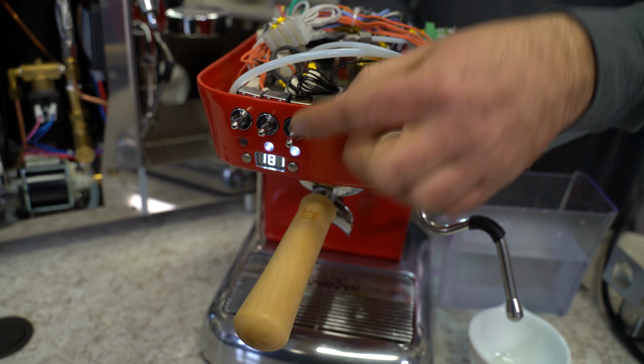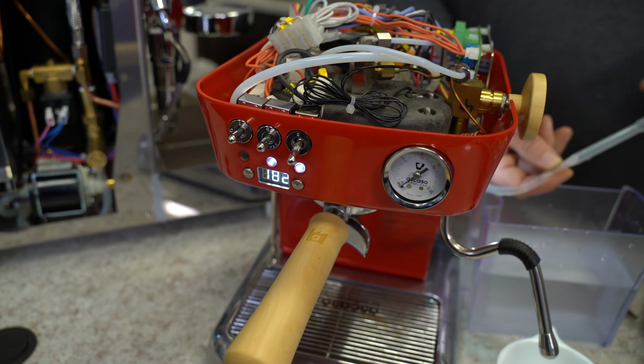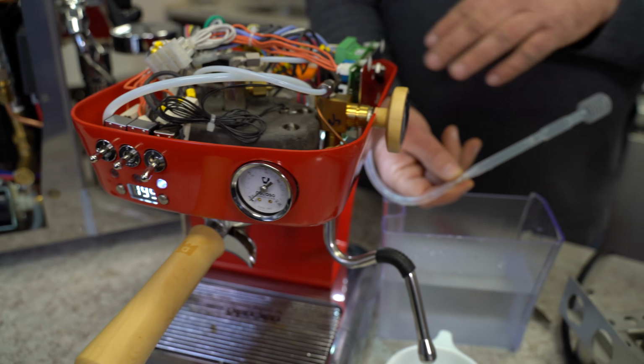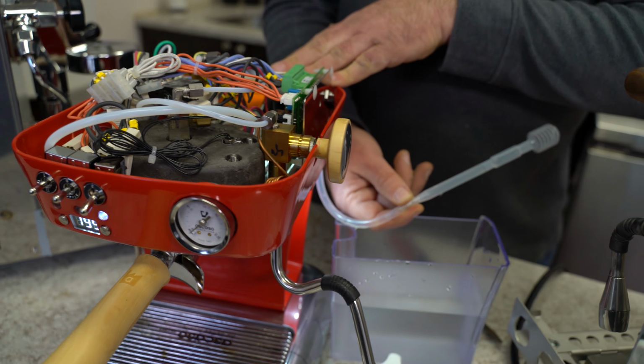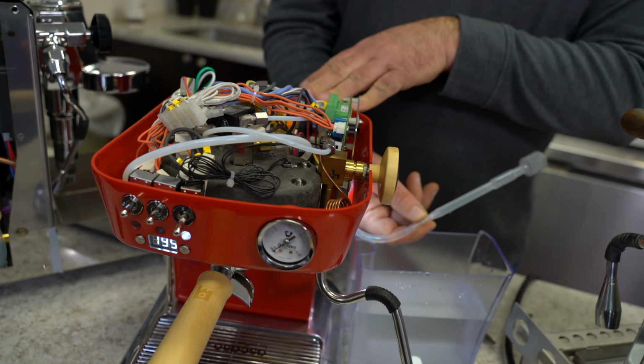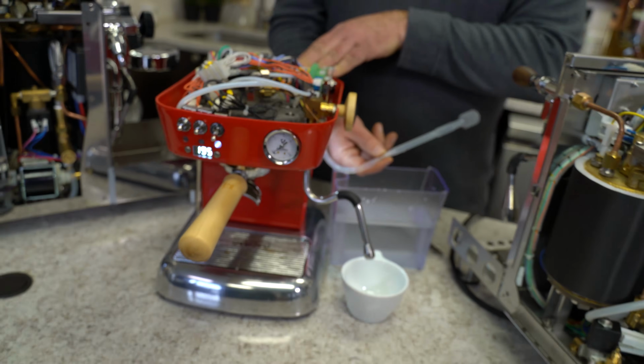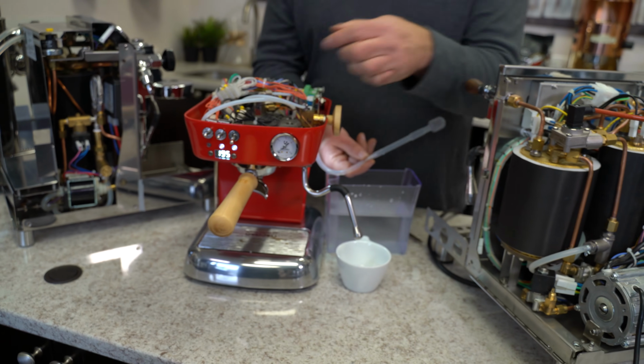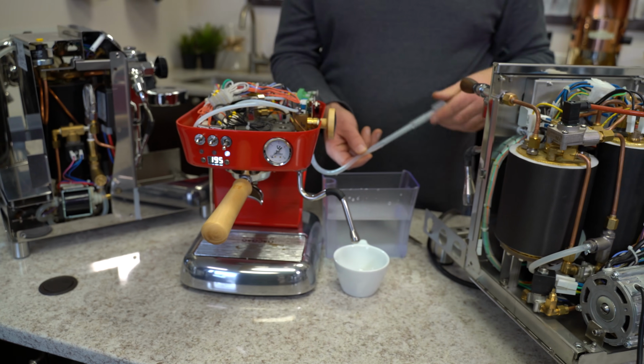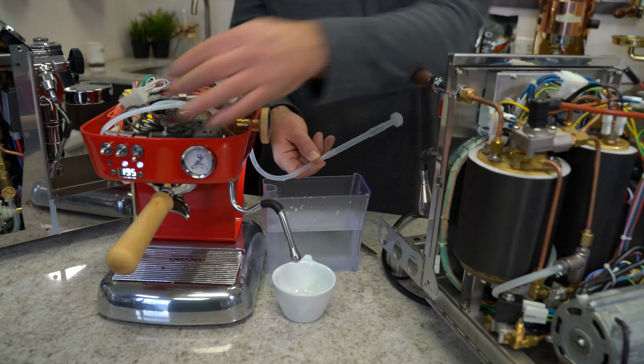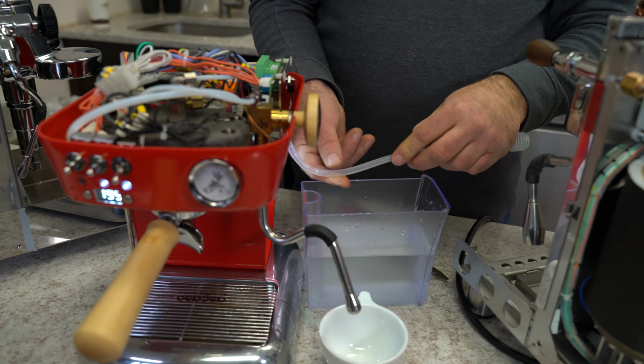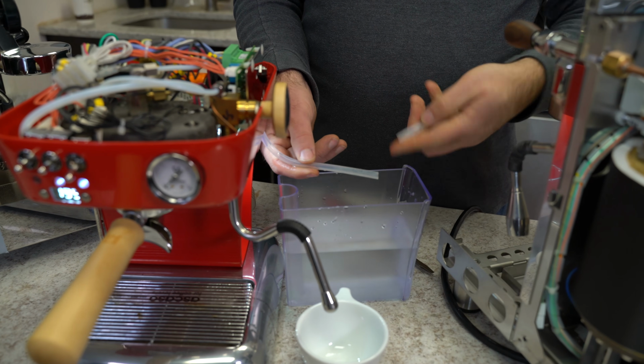Turn that up, and as you can see, this machine is not going to do anything until it heats. Now, we heard the pump motor noise before. That sound was actually pretty good and indicated that there's an air pocket in the pump. Okay, so now I'm pumping, and now it started sucking a little bit. I can see the suction happened right here. As soon as that happens, see, there's no water coming out.